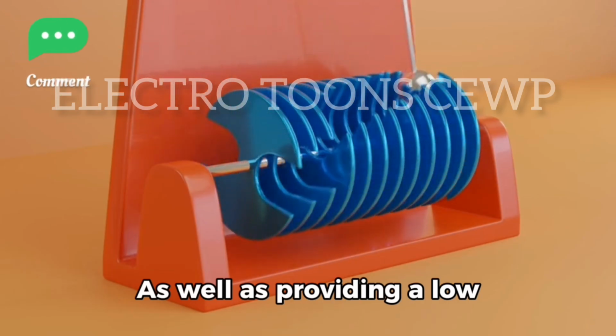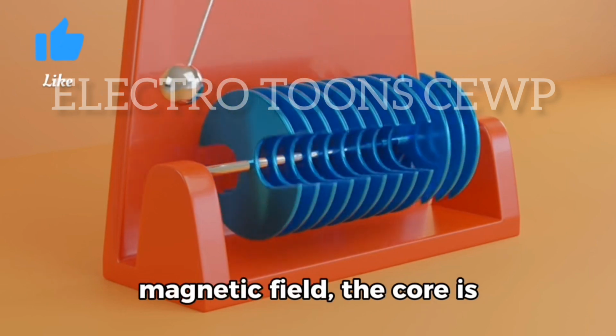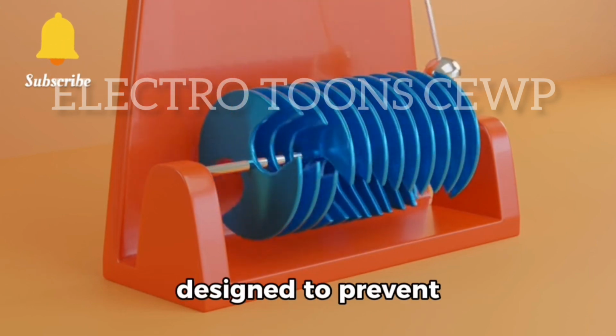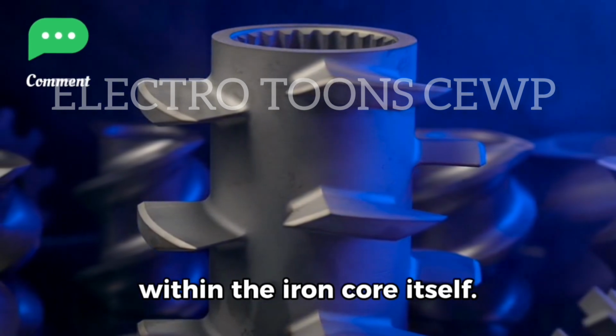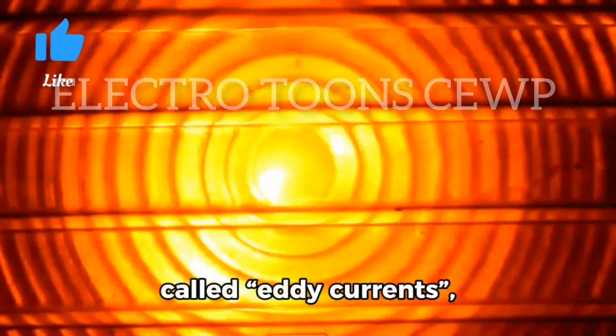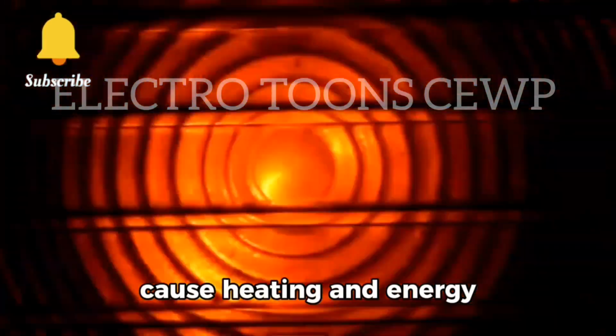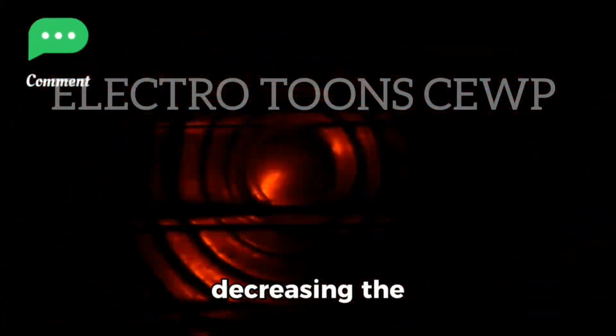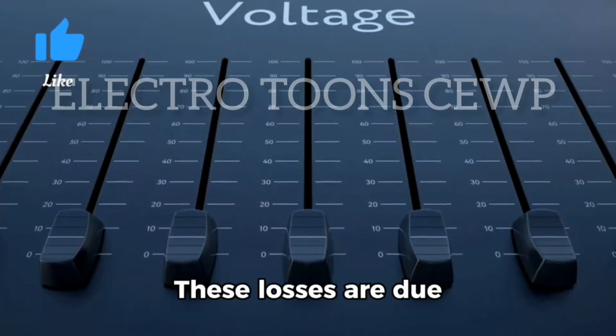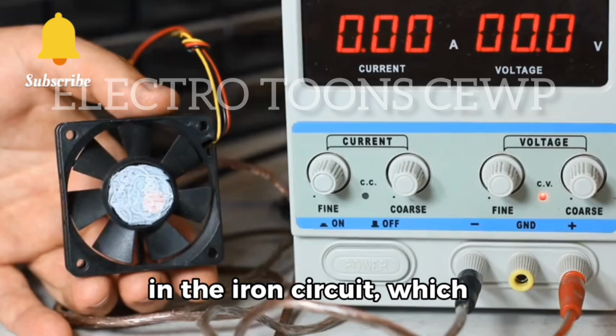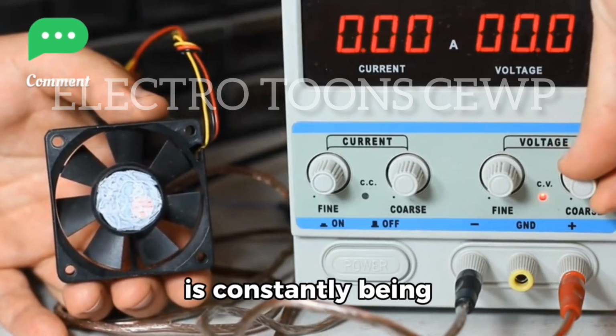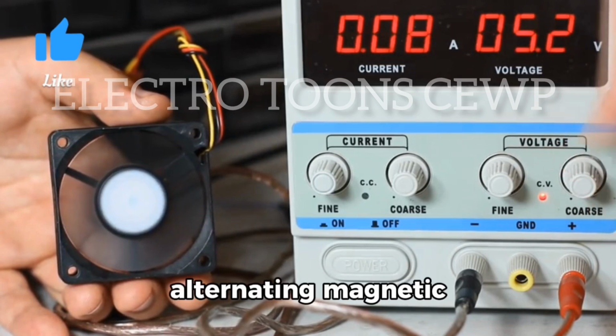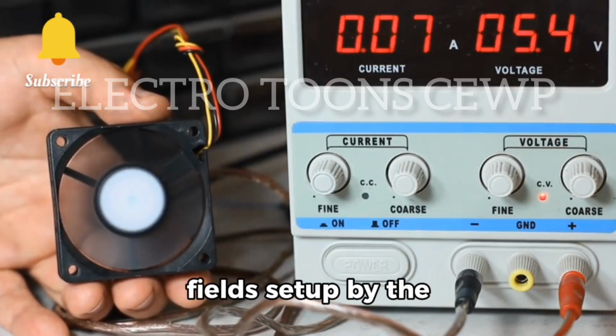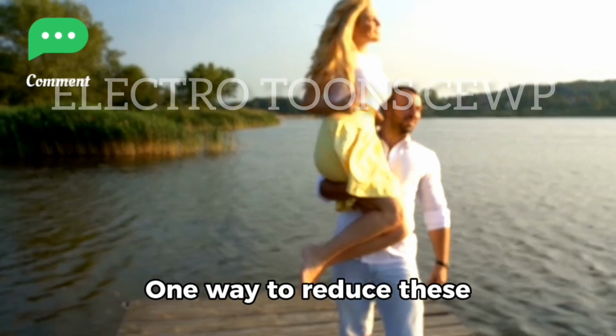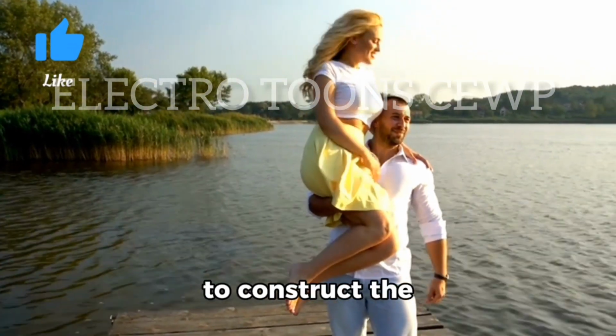As well as providing a low reluctance path for the magnetic field, the core is designed to prevent circulating electric currents within the iron core itself. Circulating currents, called eddy currents, cause heating and energy losses within the core, decreasing the transformer's efficiency. These losses are due mainly to voltages induced in the iron circuit, which is constantly being subjected to the alternating magnetic fields set up by the external sinusoidal supply voltage. One way to reduce these unwanted power losses is to construct the transformer core from thin steel laminations.